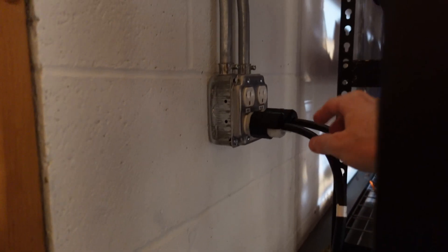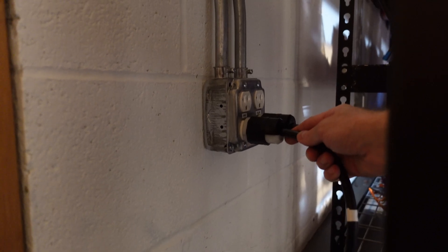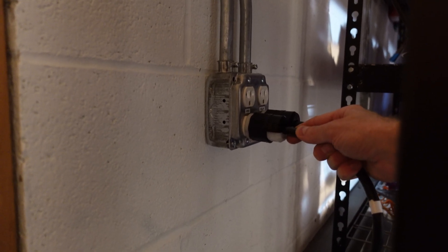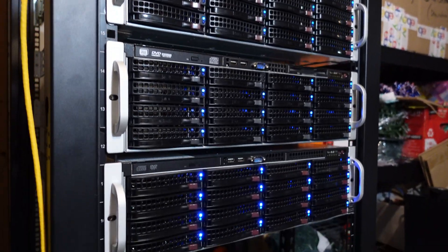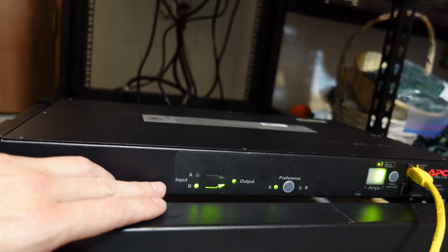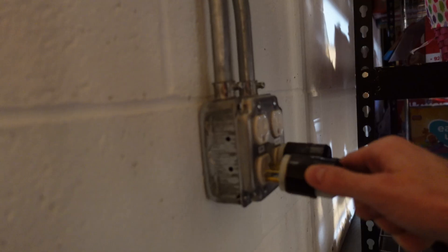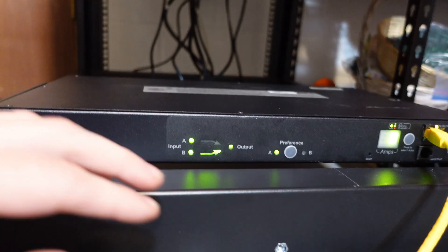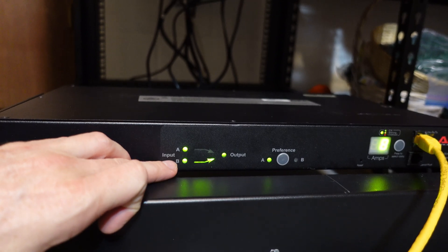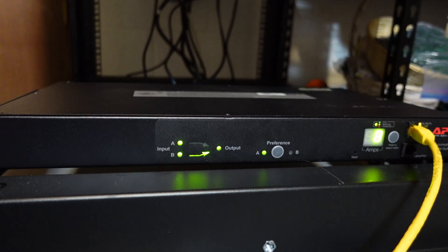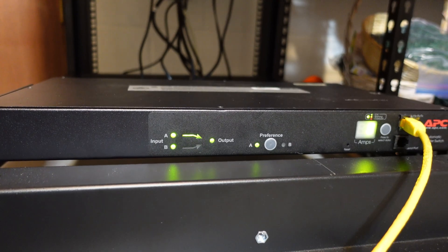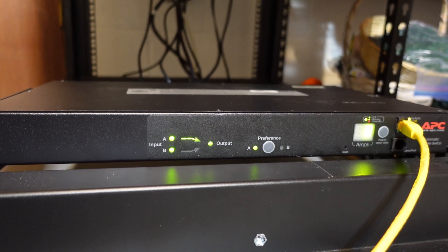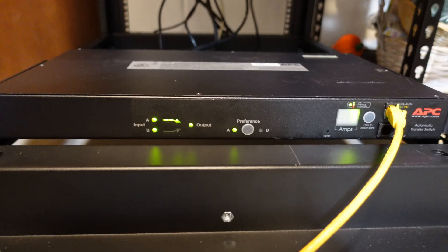So let's say we had a grid failure and the power goes out for source A. You can see the servers are still running and the transfer switch has switched to input B. So now we can plug A back in, and we see we have power on source A again, but it hasn't switched back just yet. It's delayed for a few seconds here. And there you go. You saw and heard it switch back to source A.